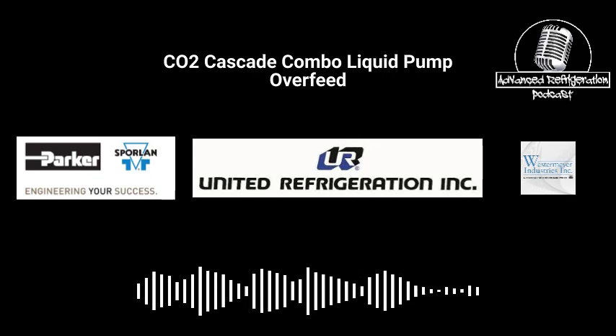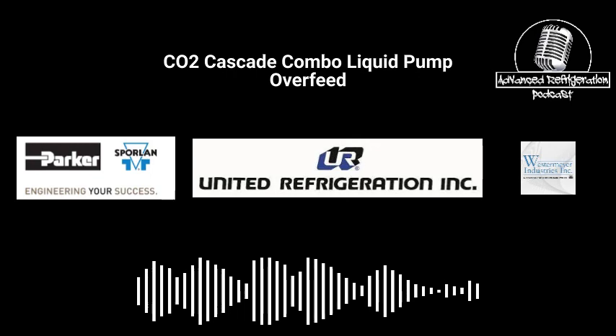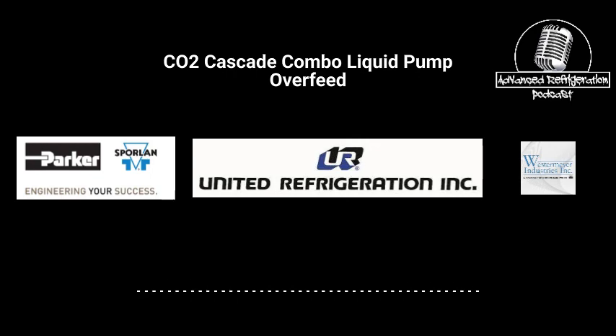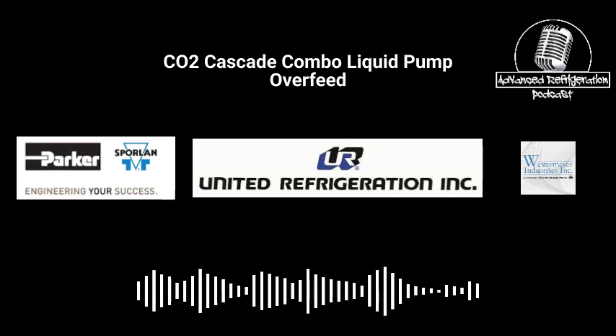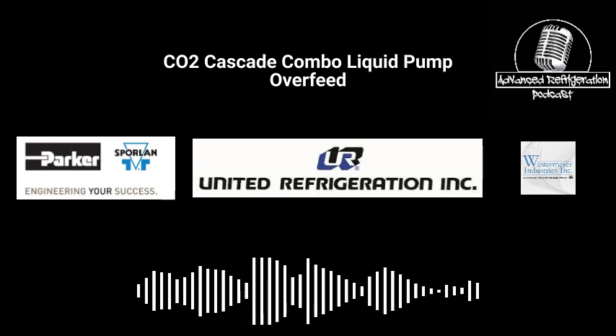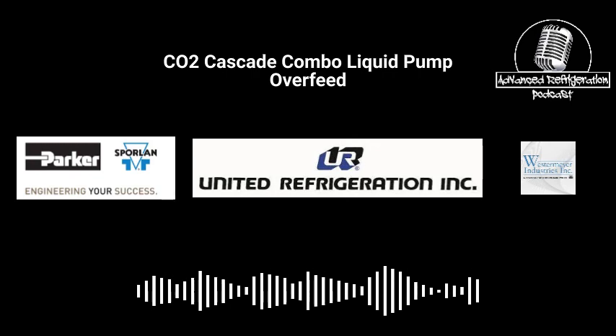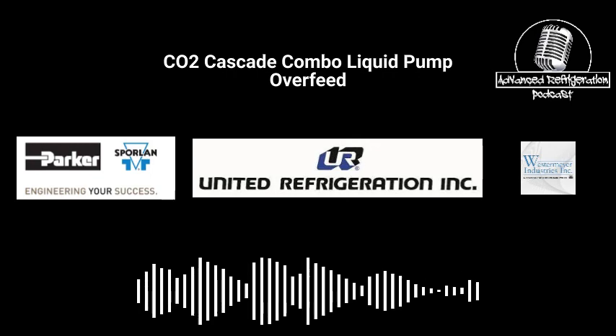And it's interesting because if anyone's ever worked on the liquid pump overfeed at the Walmart, typically those all have low temp compressors on there, because they bring the CO2 temperature down to -20 or -22 or something like that, and they're able to refrigerate their low temp. This one's just a little bit different. It's still utilizing an HFO or an HFC compressor, but instead of having low temps on there, because it's a combo cascade and liquid pump overfeed, they're basically utilizing the medium temp CO2, like the temperature that you would need.